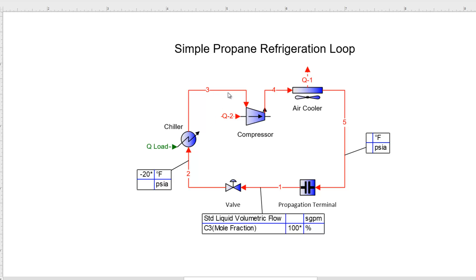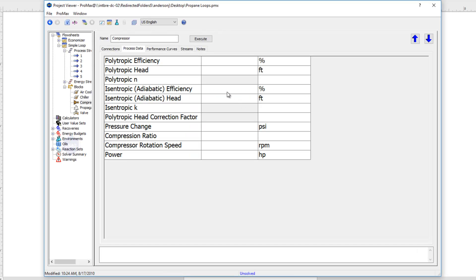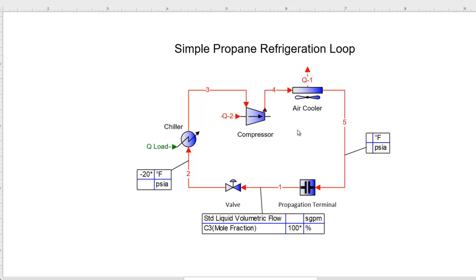Continuing from stream 3, we next run into our compressor. I'll open the compressor and set 75% adiabatic efficiency as an example. The compressor's job is to compress us up to a pressure high enough so that our air cooler can then liquefy or condense all our propane. Depending on how cold our air cooler can get us, that's really what's going to define our compressor outlet pressure.